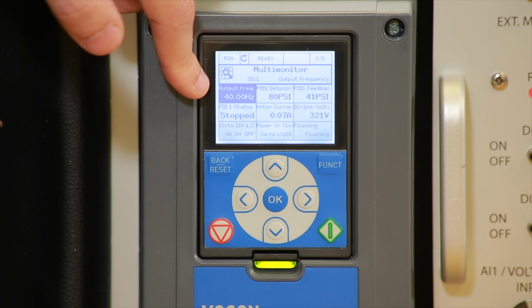Maximum frequency, we're going to program to 60 hertz in our case. We could go up to 320. Acceleration time, it's asking now. 5 seconds is default. We could change it to 10 seconds by going left here and down to 0. So 10 seconds. Deceleration time, we can leave it at 5 seconds, or we could change it to whatever we like. We can leave it at 5.